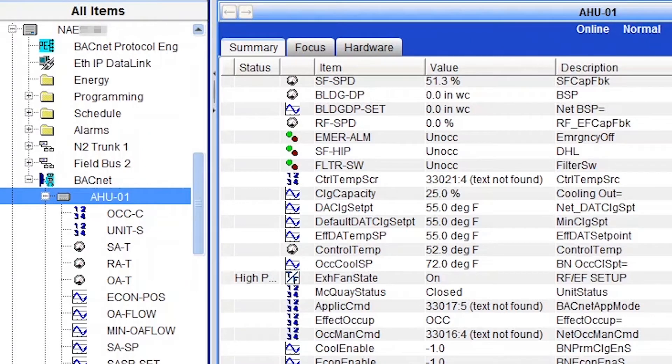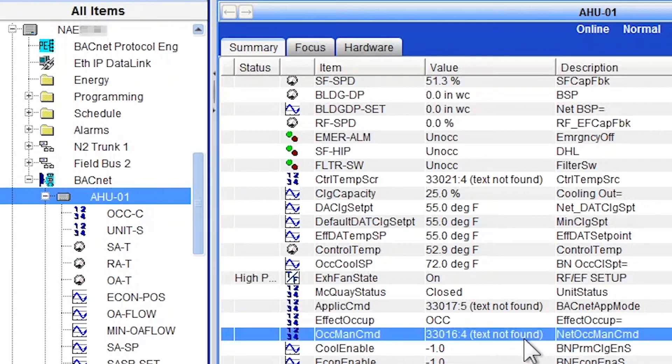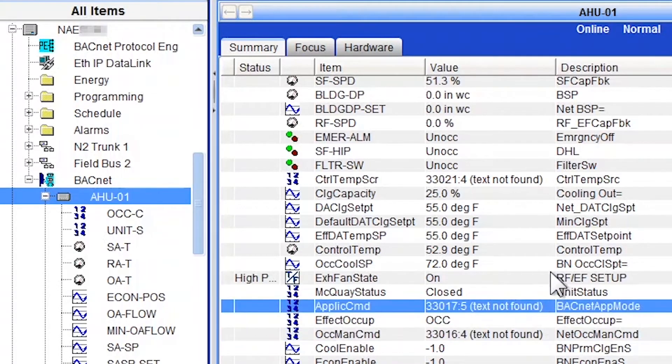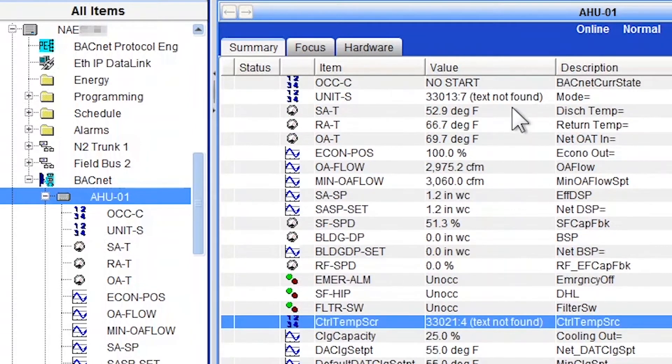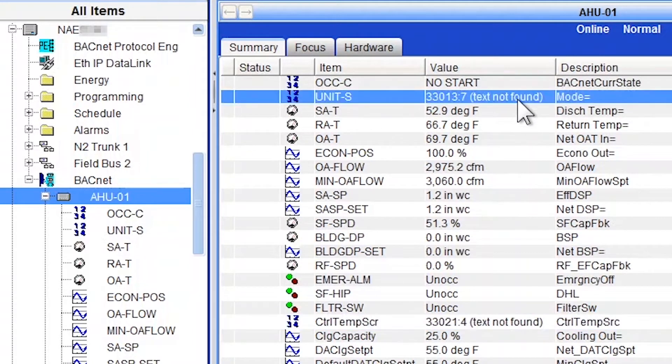Here I have a McQuay or now Daikin Air Handler BACnet device that was mapped in Metasys, and you can see that we have a couple of multi-state points not reading correctly. Okay, so let's fix it.